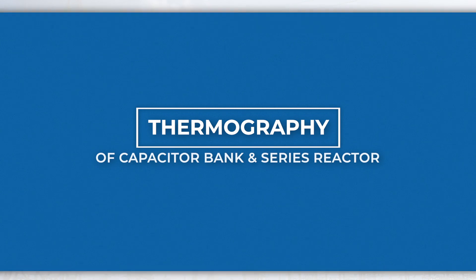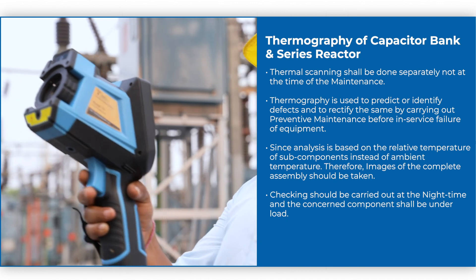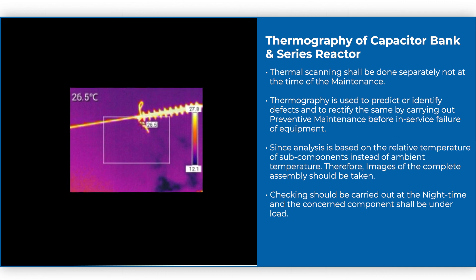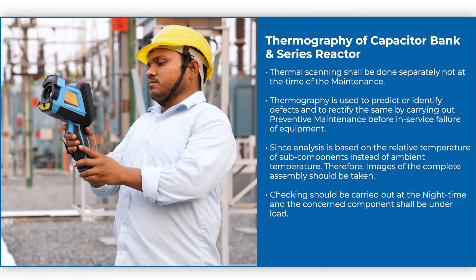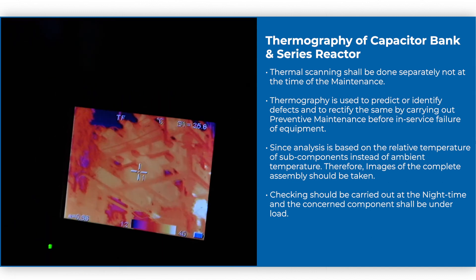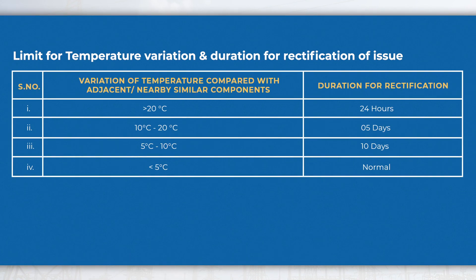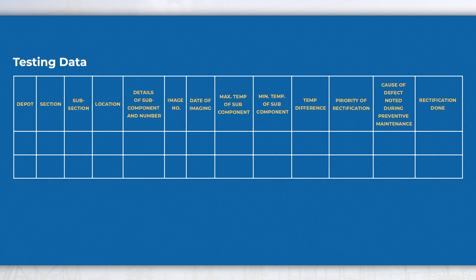Testing data may be recorded in the specified format for further investigation and future reference. Thermography of capacitor bank and series reactor: thermal scanning shall be done separately, not at the time of maintenance. Thermography is used to predict or identify defects and to carry out preventive maintenance before in-service failure. Since analysis is based on the relative temperature of subcomponents rather than ambient temperature, images of the complete assembly should be taken. Checking should be carried out at night time and the concerned component shall be under load. The limit for temperature variation and duration for rectification of the issue is given in the table.